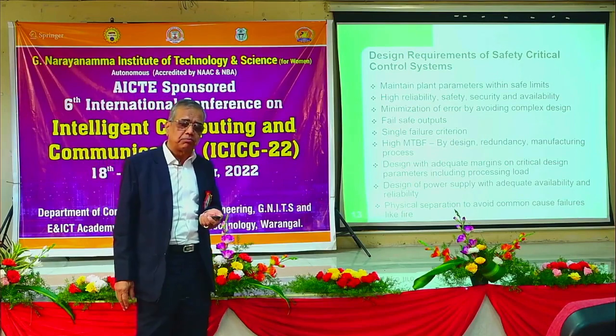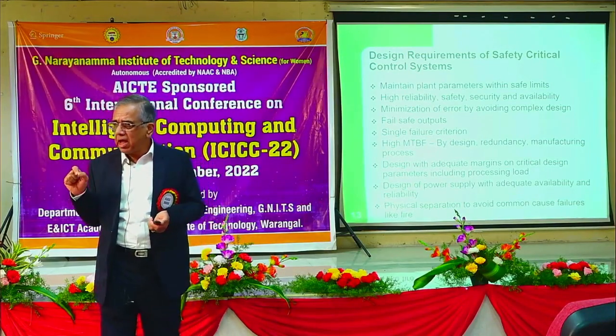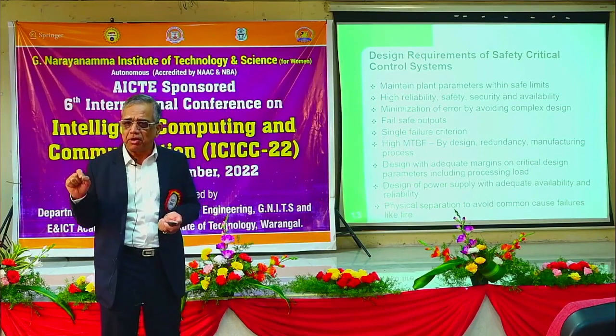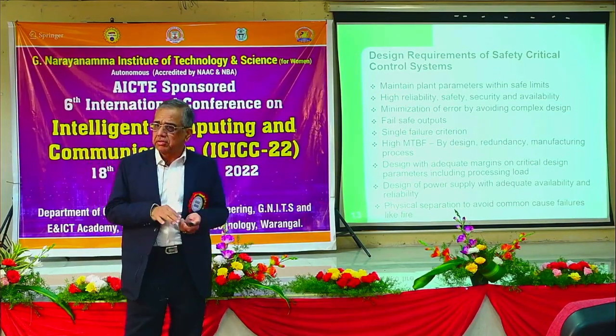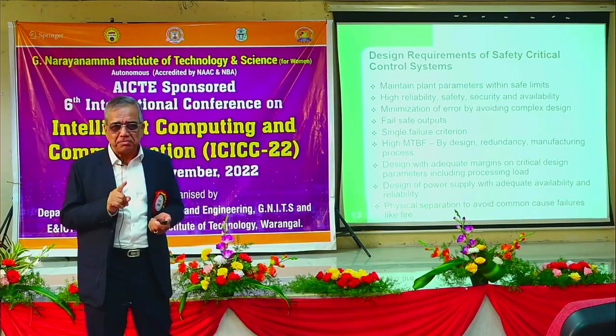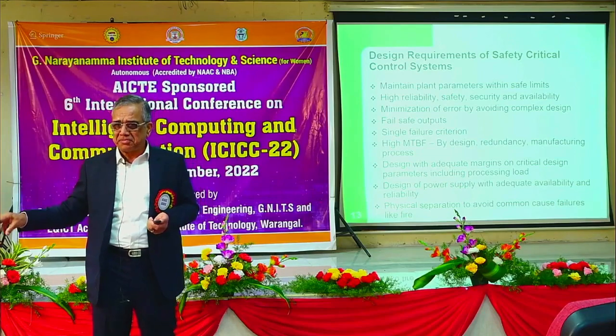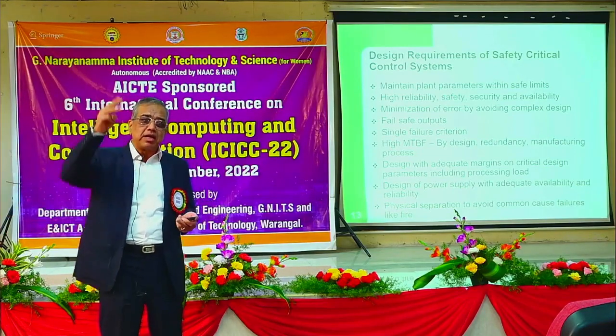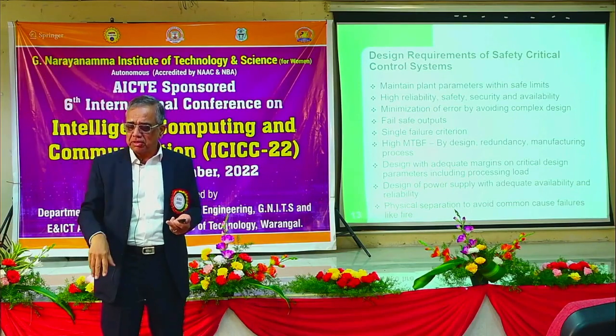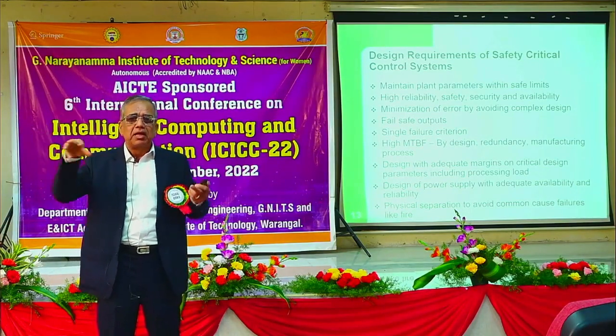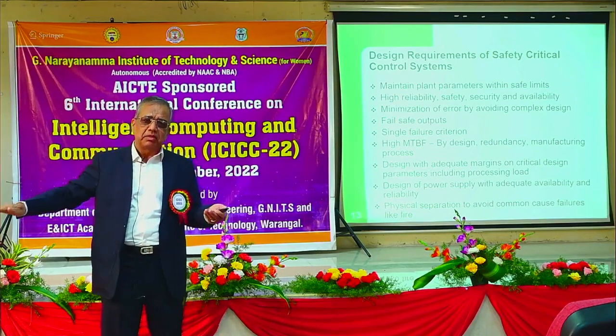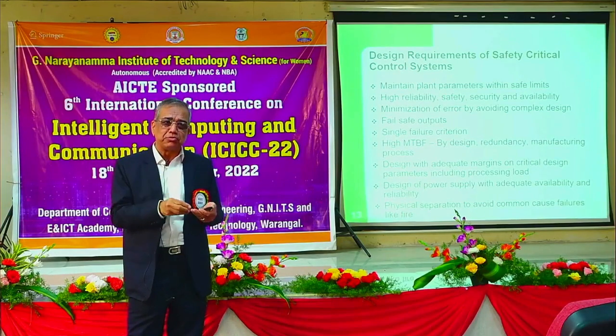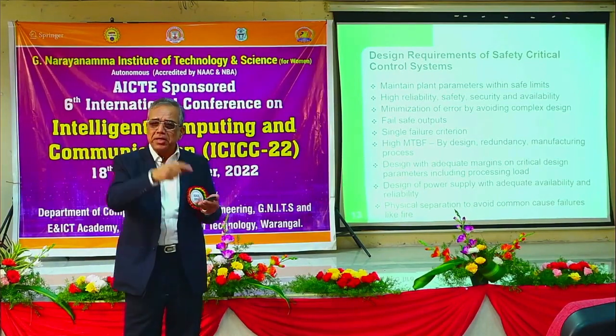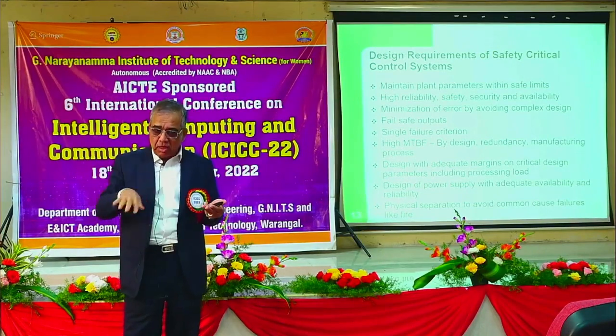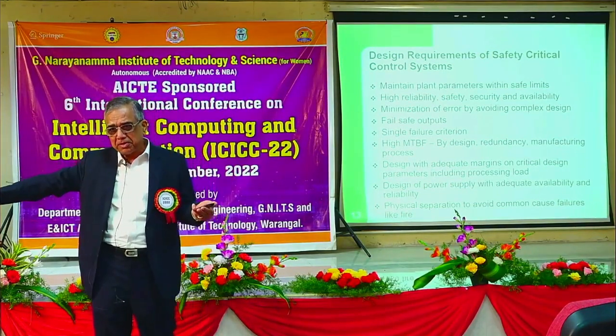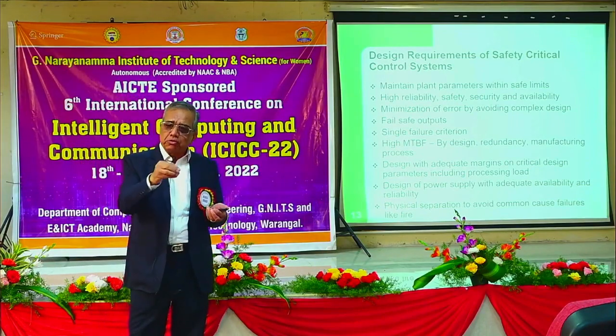Single failure criteria. No single failure anywhere in the component or system should lead to failure of the control system. So, we do not use a single control system, we use triplicated control systems. There are 3 systems, there are 3 sensors. Suppose it is a pressure, you will have 3 pressure sensors coming to this. In each system, we will have 3 boards. Suppose there is an analog input, it will not be one analog input, there will be 3 analog inputs, and those 3 sensors will come to this, again go to this, again go to triplicated systems. And then you do median selection.